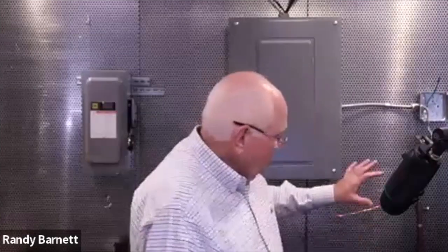Thermostats, 48 inches. So if you think about it, we've got receptacles at 18 inches, and we've got a lot of our switches, thermostats, and so forth at 48 inches. Push buttons, 48 inches. Clock outlets, 96 inches. Now, fire alarm pull stations, 48 inches. So just like the switches, I want to be able, readily accessible, I can run up and grab it and pull that handle down as I need to, right? So for fire alarms, gongs, bells, horns, and lights and so forth, I'm going to mount them on my wall. It's got to be a minimum height, it says, of 80 inches, but it can't be any closer than 6 inches to the ceiling then. So that's some pretty good information.